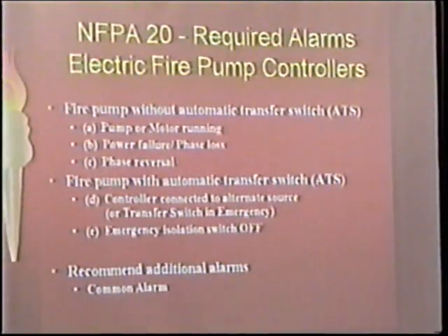Fire alarms. You catch a lot of grief when we get to jobs and we start telling the alarm contractors that they're short points. And I understand it's not their problem. It's because the designers of the alarm system or whoever laid it out didn't put them on their drawing. And it's the first thing I tell them. I know it's probably not on your drawing, but these are the standard 3 that on electric pumps they all know they have to have. These 2 here, when we get with the transfer switch, are the ones that are always missed.